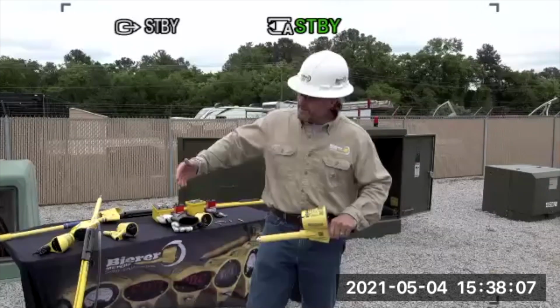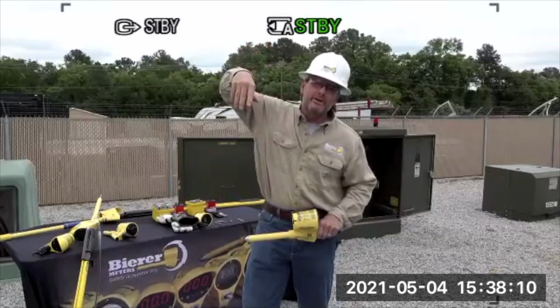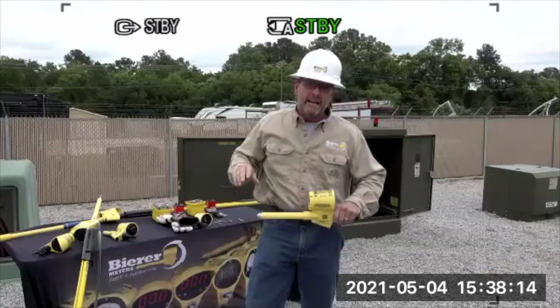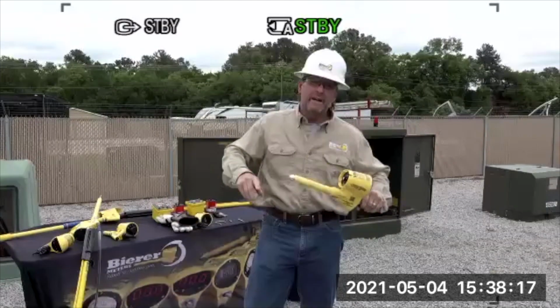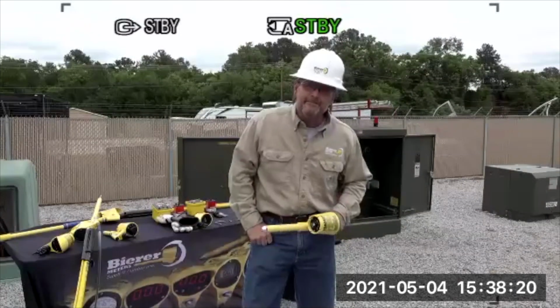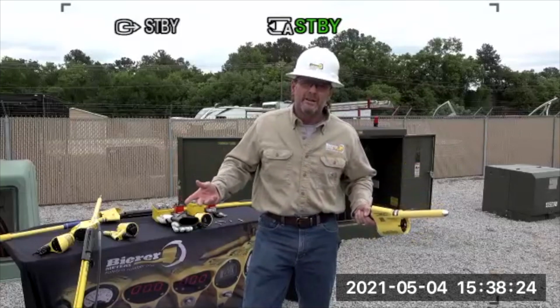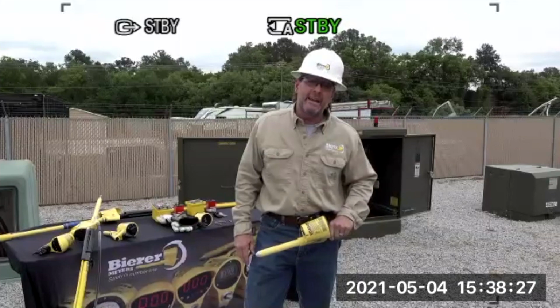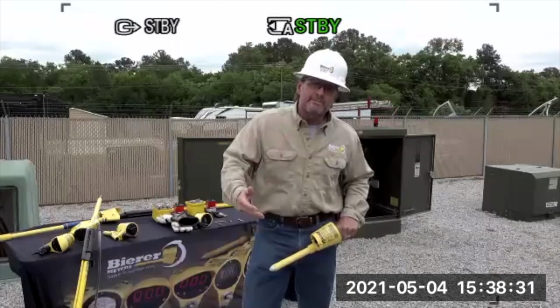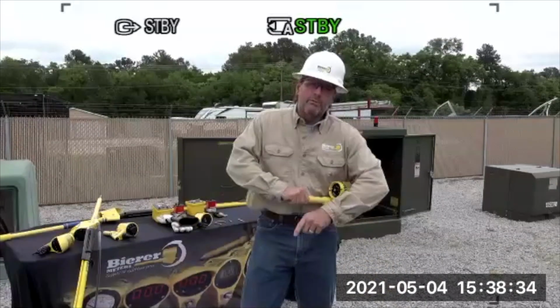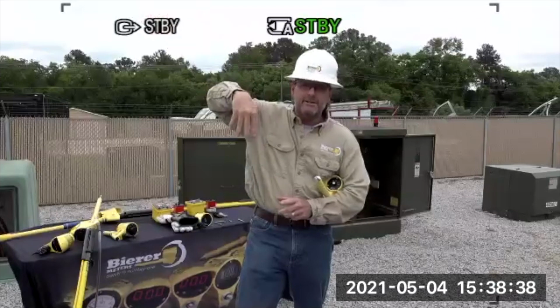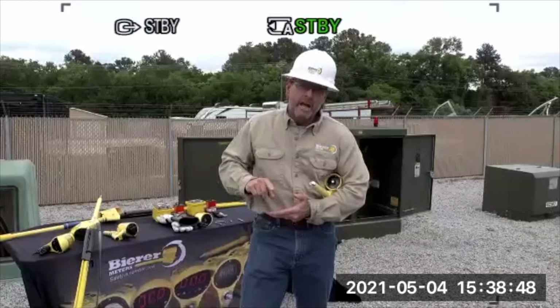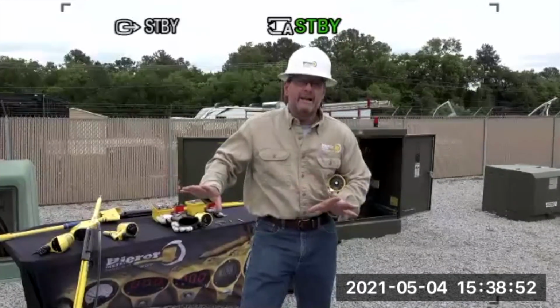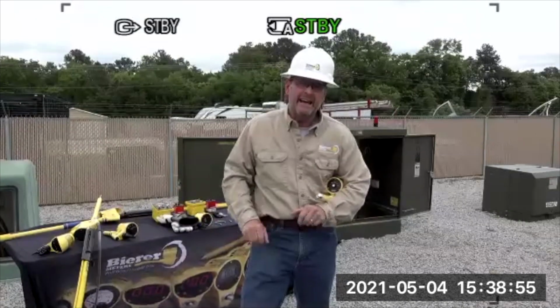Not only that, but if you're in a tight cabinet, maybe on an underbuild with transmission lines, or on distro with an underbuild, and you've got a non-contact tool verifying a particular conductor de-energized, you're going to get something on that tool no matter what. Non-contact tools are just no good. They're very dangerous. The line worker is presumptuous, basically guessing. Remember, we want to look for a lack of nominal, a lack of induction, and a lack of backfeed on a particular conductor. A non-contact tool does not do that accurately.